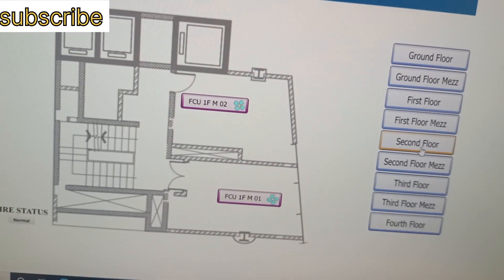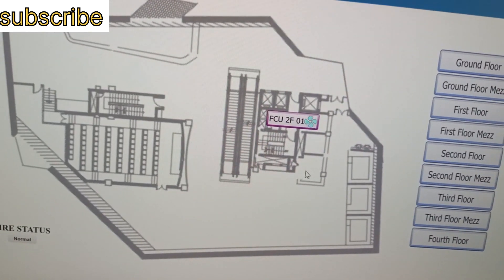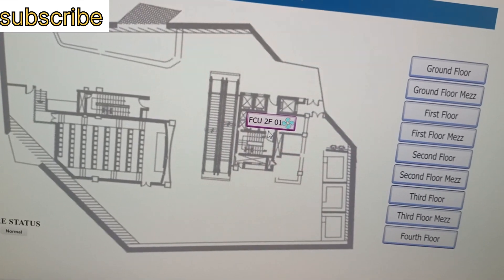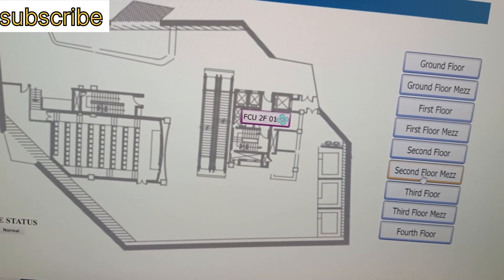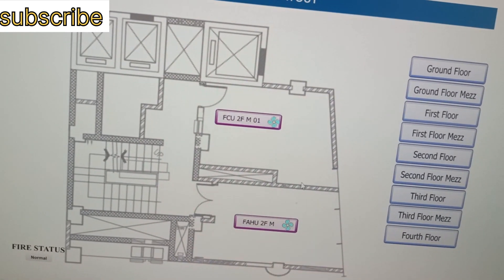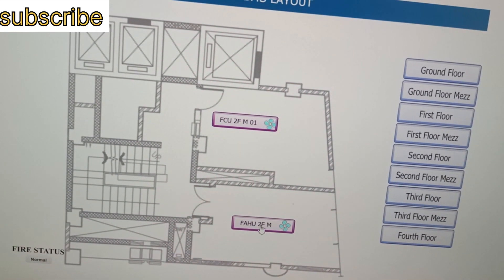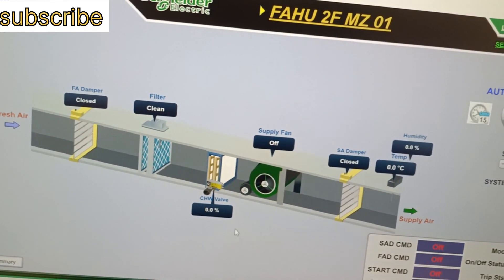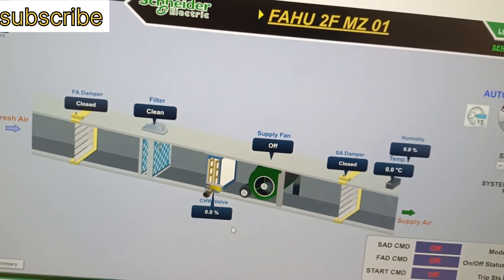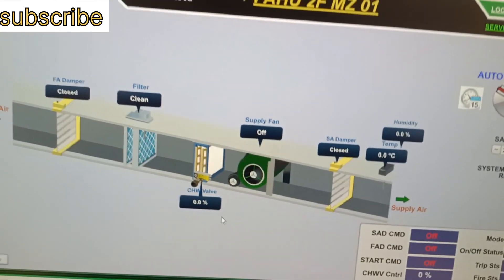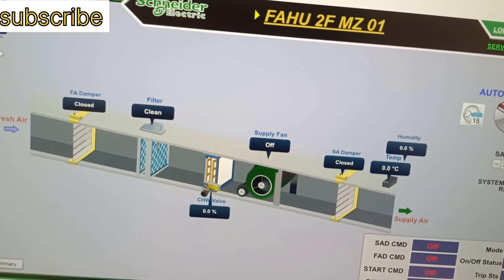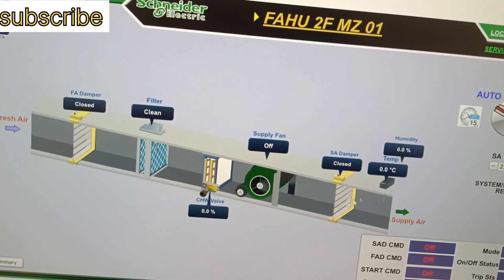On the second floor there is only one FCU showing, and it is in running mode, so that is fine. On the second floor mezz we also have two FCUs — one is running and one is in off position, because it has been replaced with a new FCU connected to a new DDC panel and new BMS system. The cable has been disconnected from the old unit, so we need to delete it from the existing system.